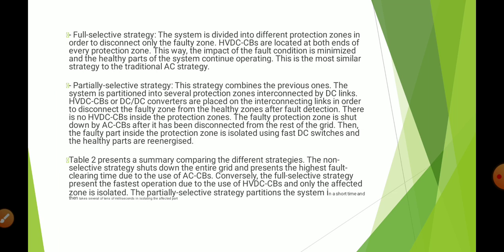Partially selective strategy. This strategy combines the previous ones. The system is partitioned into several protection zones interconnected by DC links. HVDC circuit breakers or DC to DC converters are placed on the interconnecting links in order to disconnect the faulty zone from the healthy zones after a fault detection. There are no HVDC circuit breakers inside the protection zones. A faulty protection zone is shut down by AC circuit breakers after it has been disconnected from the rest of the grid. Then the faulty part inside the protection zone is isolated using fast DC switches and the healthy parts are again re-energized.